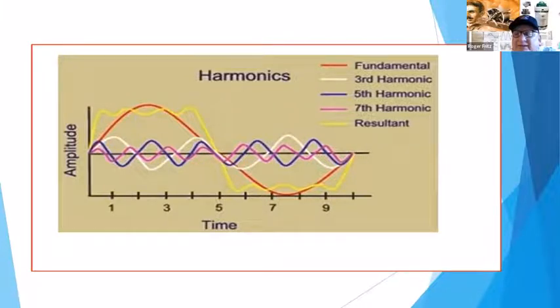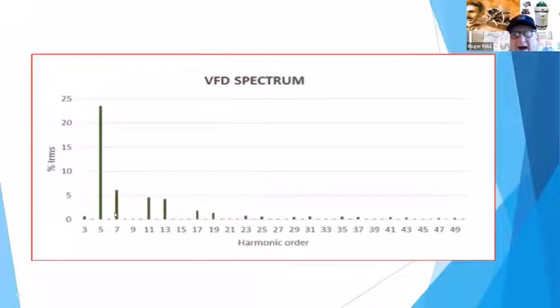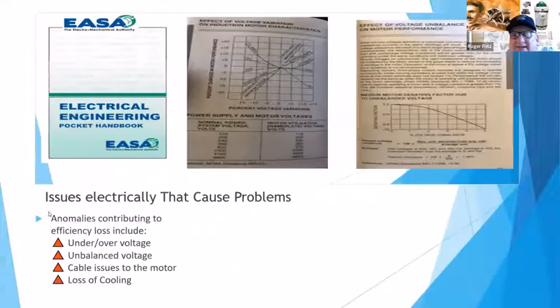power back on the solar to only 2 phases because it's cheaper than doing all 3 phases. They're putting it back to the grid, and it's changing the voltage on 2 legs up to 600 volts, and it's 480 on the other leg. That's an absolute no-no, but they kind of get by. So back to your question, have them get a quick meter and show them where these are. You can buy some fairly inexpensive harmonic meters and stick it out there.